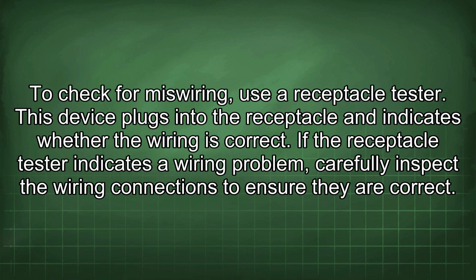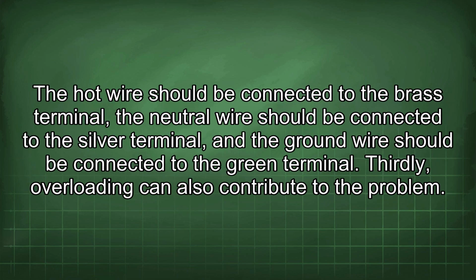If the receptacle tester indicates a wiring problem, carefully inspect the wiring connections to ensure they are correct. The hot wire should be connected to the brass terminal, the neutral wire should be connected to the silver terminal, and the ground wire should be connected to the green terminal.